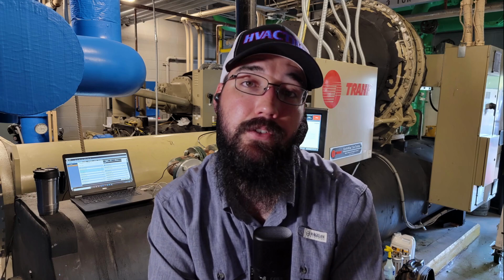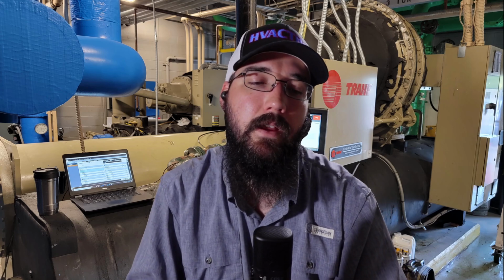Like, it wasn't a tool that I had to buy, but I can acknowledge that it would be a very useful and resourceful tool to have on site, if you have a tool that can cycle that valve without having to go through the chiller's control package, especially when you're trying to determine: is this a valve issue or is this a controller issue? Because the controllers fail too. I just find that they don't fail near as often as the valves do. Most of the controllers we have in the market so far seem to be pretty robust overall.